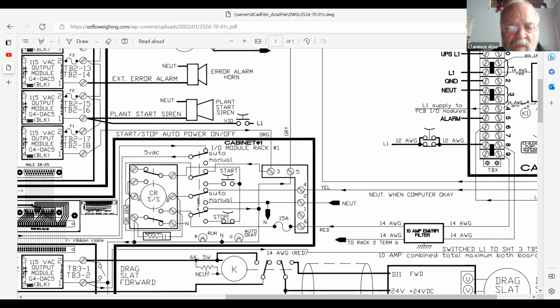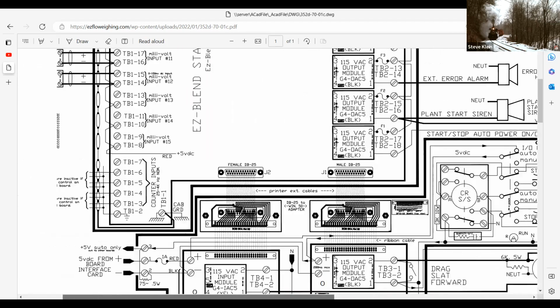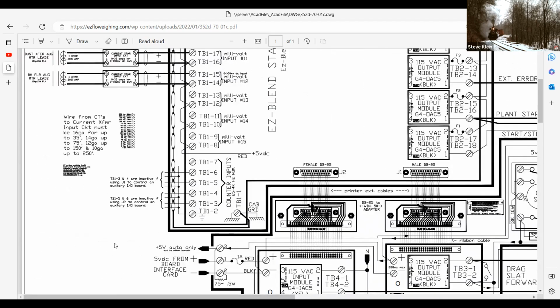Clarence? Yes. I believe that burner interlock is your exhaust fan running interlock, because you're telling that VFD to run and the burner needs to know that the fan is started. And if Dave could slide to the left, there was one note down there off the CTs I think is kind of important. It mentions on the CTs what gauge wire right there. You see that notation for how many feet away you're running from your MCC cabinet to that little contact that you're reading in, what size wire you should be using to make sure that you're not getting any voltage drop on the wire and you're getting a true reading off your CT meter. Gotta be kidding me.